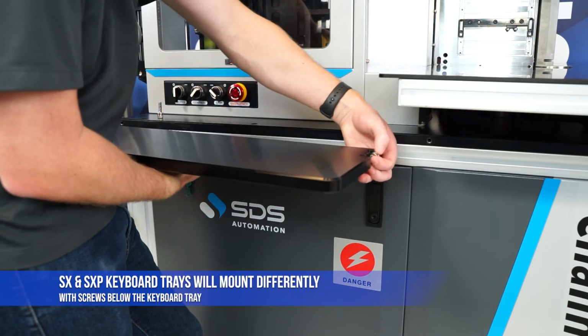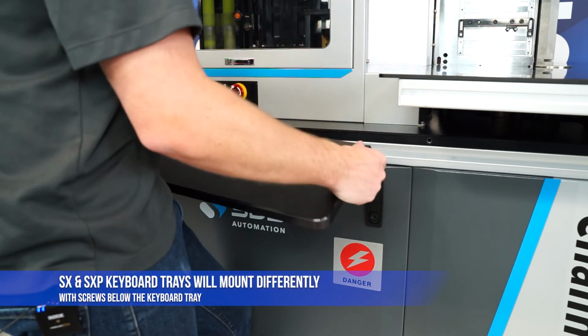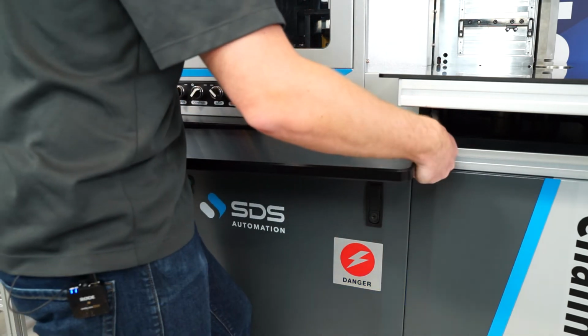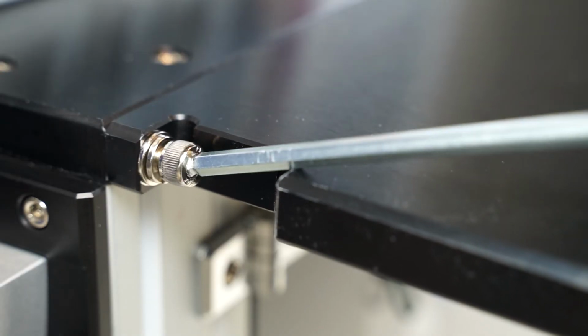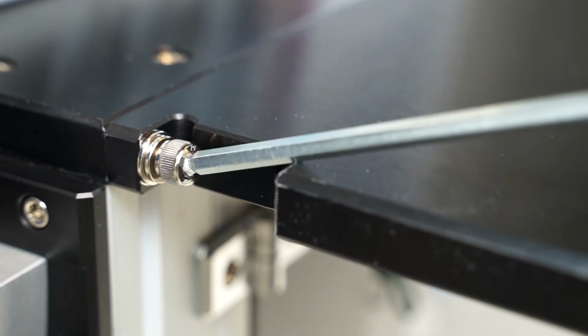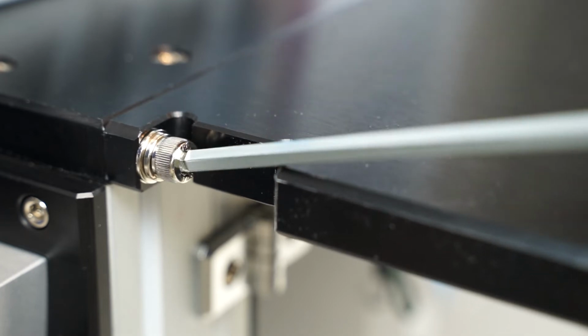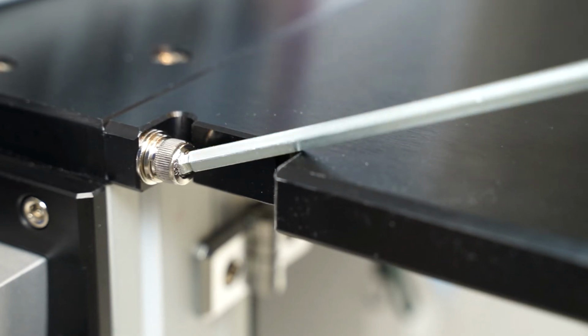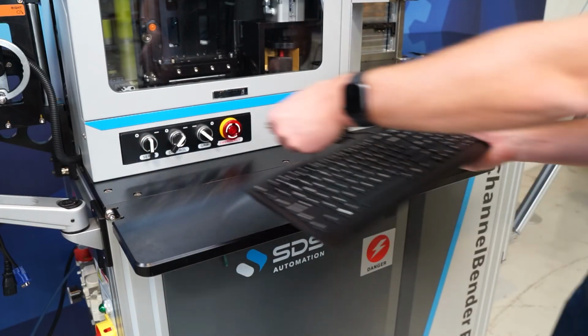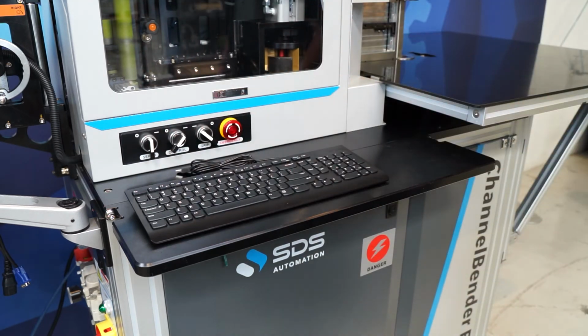Some machines have 2 screws that hold the keyboard tray onto the machine. These bolts are inserted from under the keyboard tray and tightened. This is done with a 5mm hex key. Once both screws are started, you can tighten both. Place the keyboard, mousepad, and mouse on the keyboard tray.